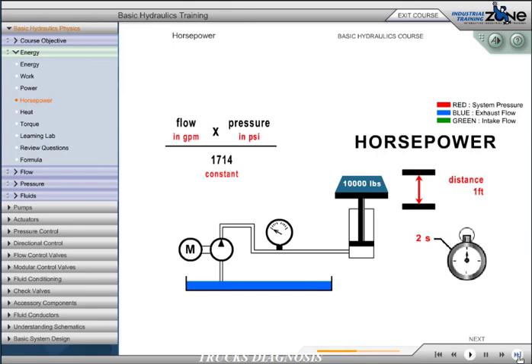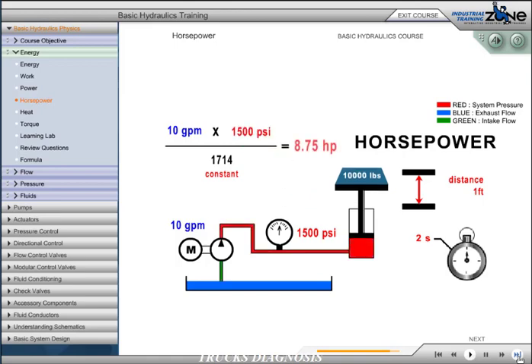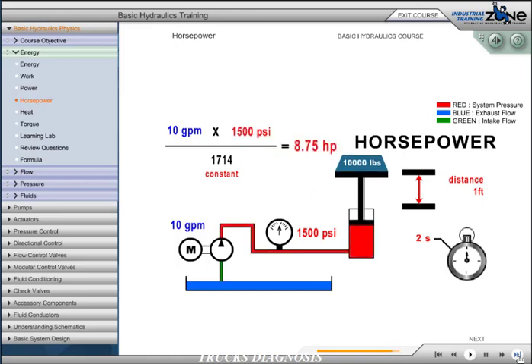To lift our 10,000 pounds a distance of 1 foot in 2 seconds, we must have a required flow rate at a specific pressure based on cylinder size and pump flow discharge. In this illustration, a 10-gallon-per-minute pump is required to extend the cylinder in 2 seconds. The pressure requirement to lift the 10,000 pounds is 1,500 psi based on cylinder diameter. Based on our formula, our theoretical horsepower requirement would be 8.75.